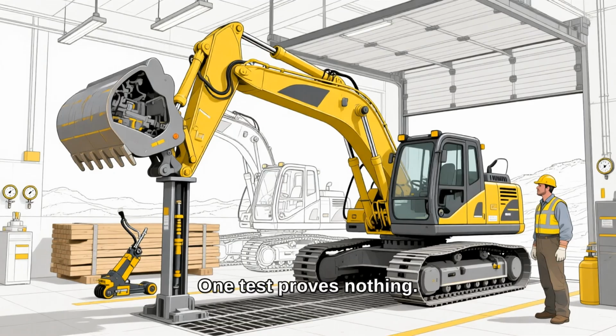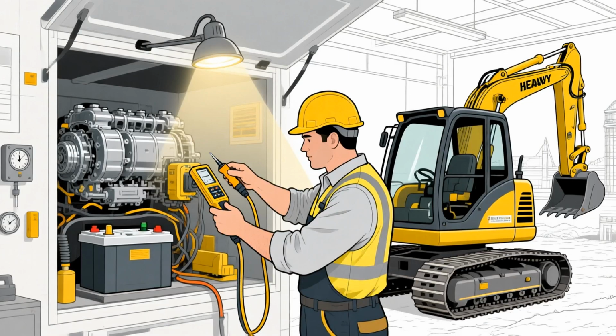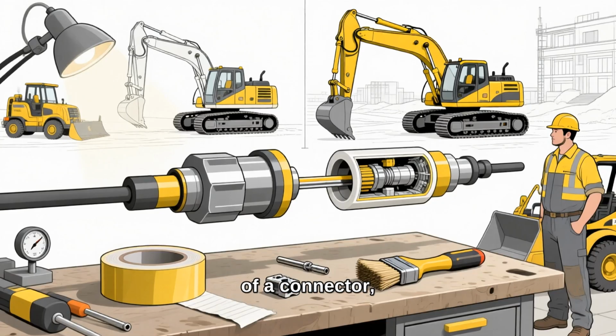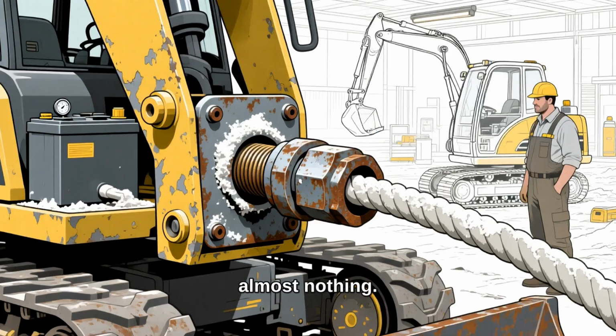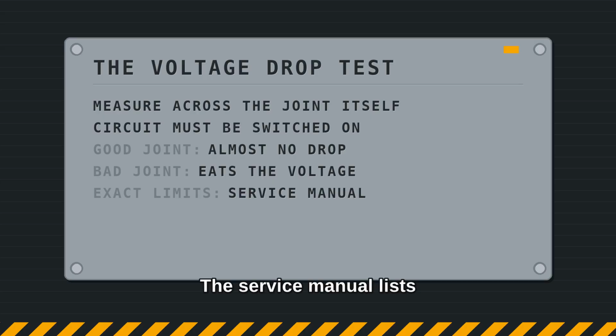One test proves nothing. So test it loaded: switch the circuit on, then measure across the connection while it's genuinely doing work. One probe each side of a connector, a splice, a ground stud. You're measuring what that joint steals. A healthy connection takes almost nothing. A corroded one eats the voltage before it ever reaches the part. The service manual lists the exact acceptable values, but the shape of the test never changes.